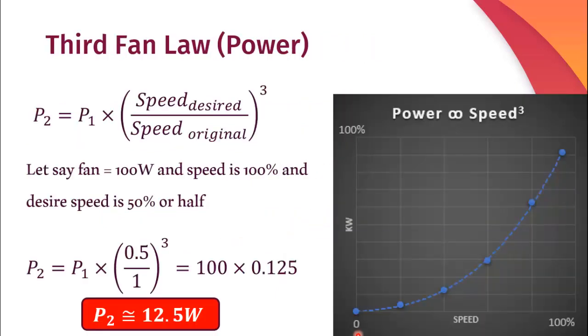Once we know how to control the speed of the fan, now let's come back to our original question, which is whether it can save energy and reduce electricity bill or not. For that, we have to refer to the third fan law, which is also called the power law, in which the power is related with the cube of the speed.